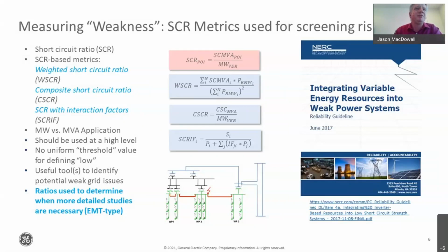So the first one is the short circuit ratio at the point of interconnection, looking at one plant. This honestly is really not the best one to use in most cases because it only looks at one plant relative to the short circuit capability.